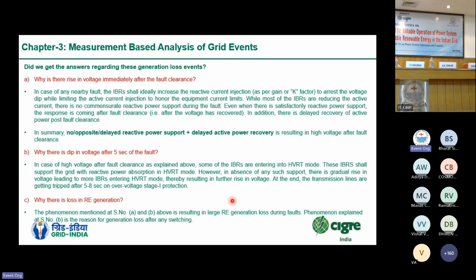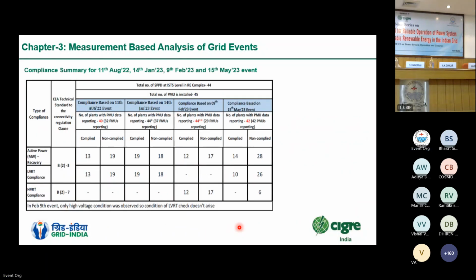And why is there loss of RE generation? Because of this high voltage post fault clearance, we suspect that most of the IBRs are entering into HVRT mode, and then there is no support from the IBRs even in the HVRT mode. So because of this, the plants or the IBRs are getting disconnected on HVRT. This table provides a brief summary of, out of 44 plants, how many were compliant and how many were not complying with the specified requirements. We can see that almost 50% of the plants, or even more than 50% in some of the events, were not complying with the requirements specified in the CEA connectivity standards.